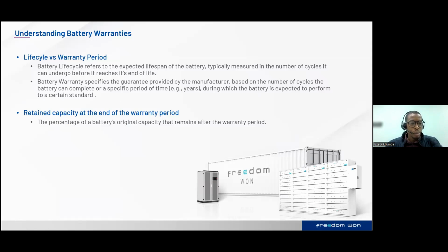Then we also look at the battery warranty, which specifies the guarantee provided by the manufacturer based on the number of cycles the battery can complete or a specific period of time. So it refers to the manufacturer assuring you that the battery should be able to perform according to the specified cycles, or those are translated into years, during which the battery is expected to perform to certain standards. And if the battery does not meet those expected performance standards, then the manufacturer would replace or repair that particular unit.